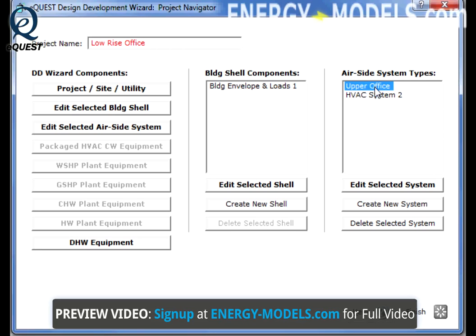We're going to cover a number of possibilities. Before we get started, we need to differentiate the difference between systems and plants in eQuest. Simply put, systems define air side components and plants define refrigerant side components. In eQuest, when modeling packaged air-cooled equipment, the system and the plant are synonymous, as in our upper office system.